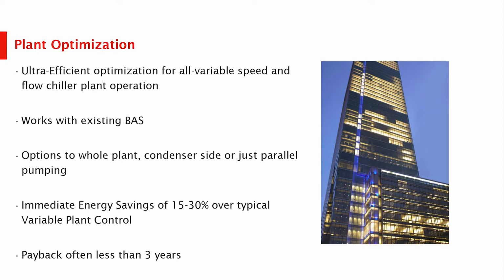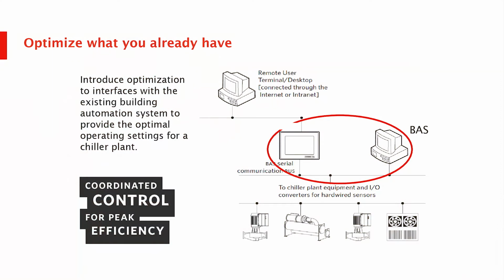So ultra-efficient optimization is about all variable. Really, we look for centrifugal chillers, much easier to modulate than screw chillers, or certainly absorption would be a different challenge totally. We want to work with the BAS system as an industry generally. This is not a threat to the BAS, it's about complementing what you already have. And consider the whole plant, condenser, pumping, whatever aspect. You don't have to make the whole decision. You can do smaller pieces as a start. Typically, we would see 15 to 30% savings, and that's a pretty defensible number depending on the way it works.